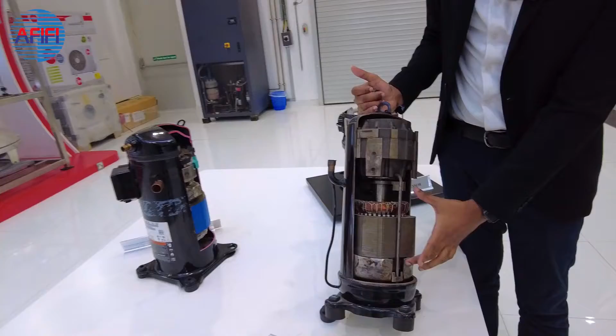So this is the compressor that we use there. It's a typical scroll compressor, only that the winding is different and there are some additional oil return lines. All of these are designed for operation on inverter boards, so this cannot run directly on electricity. You need an inverter drive board. This is a DC drive motor, designed for inverter, so variable frequency operation. Simple, like a VFD, just that these are more like a BLDC motor rather than induction motors.